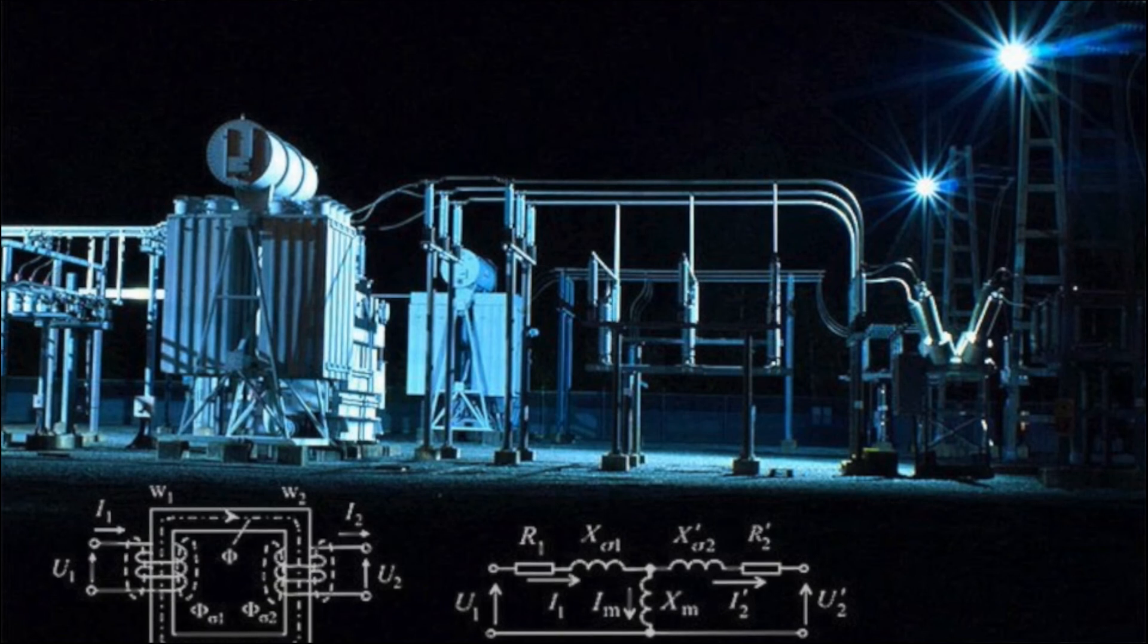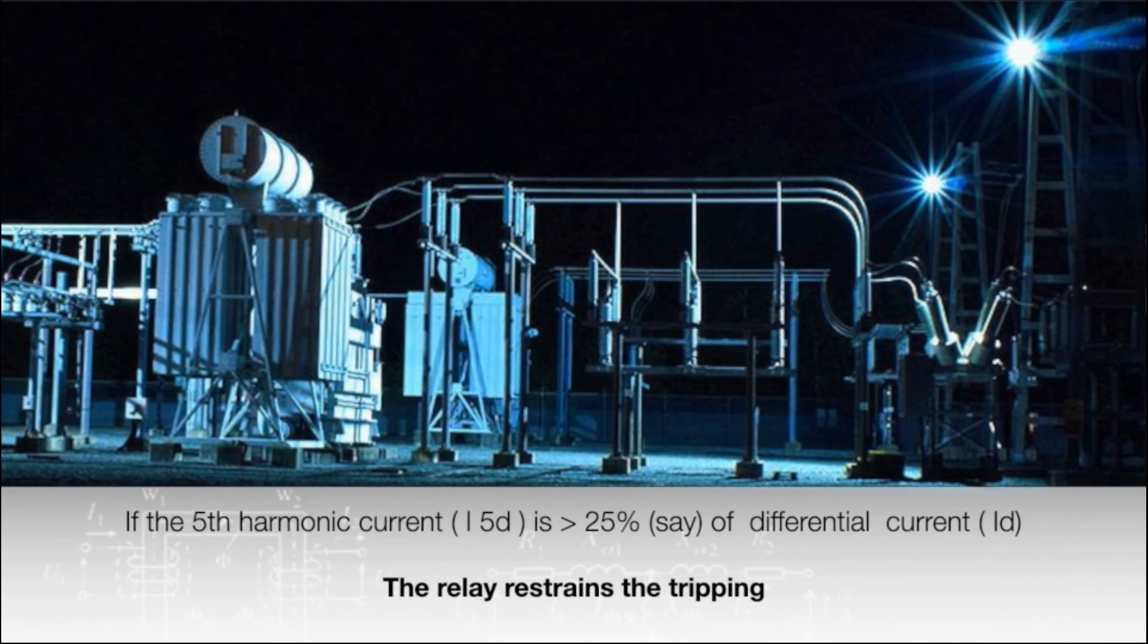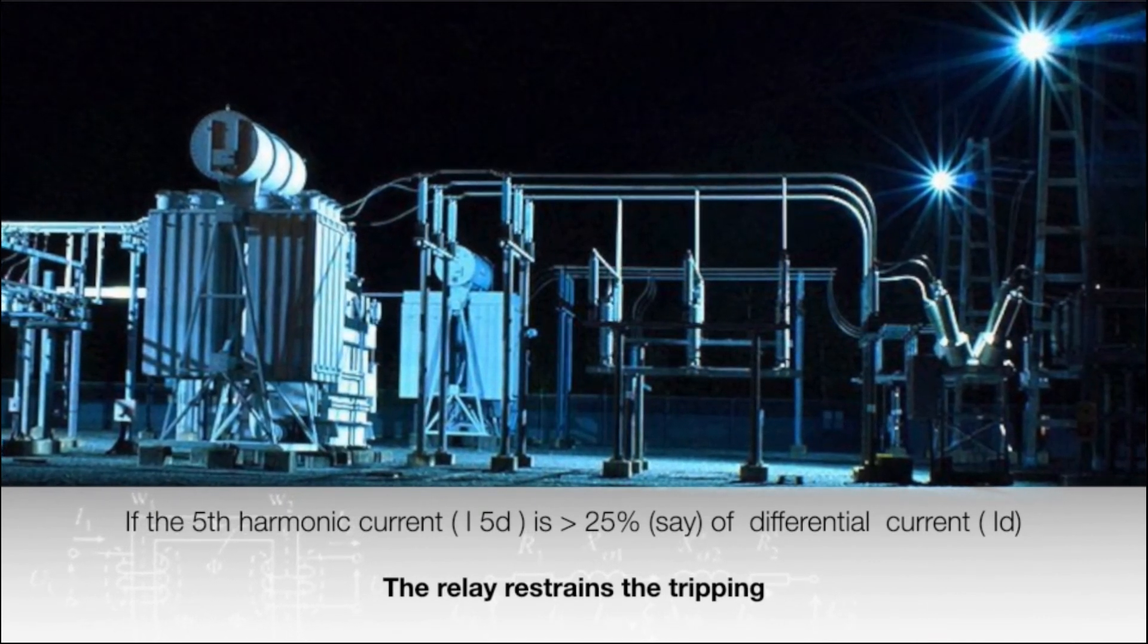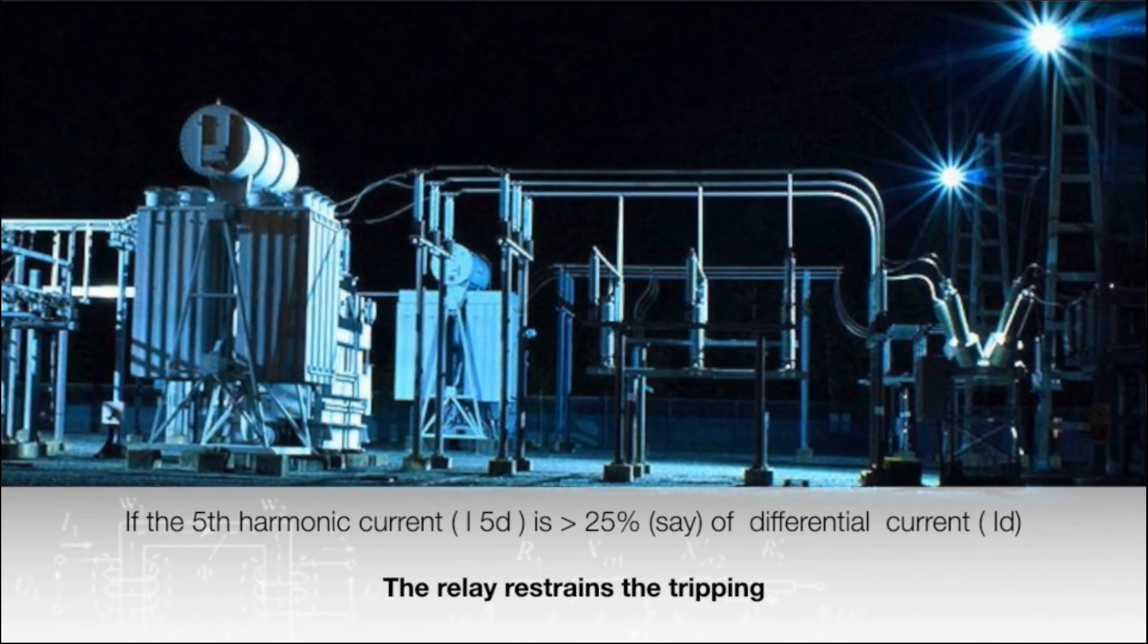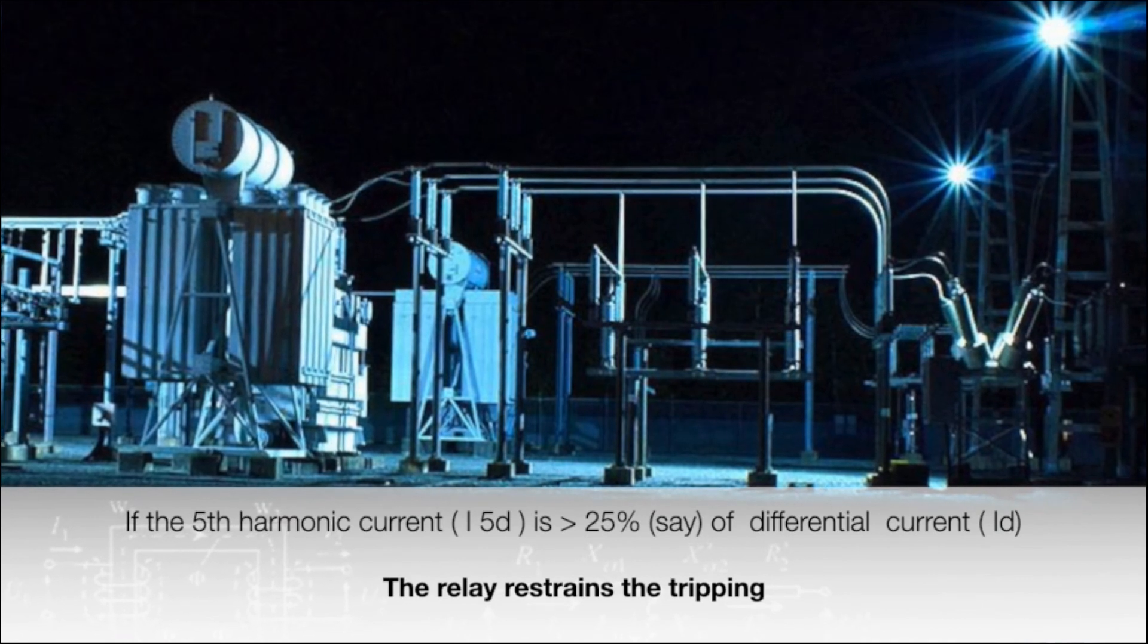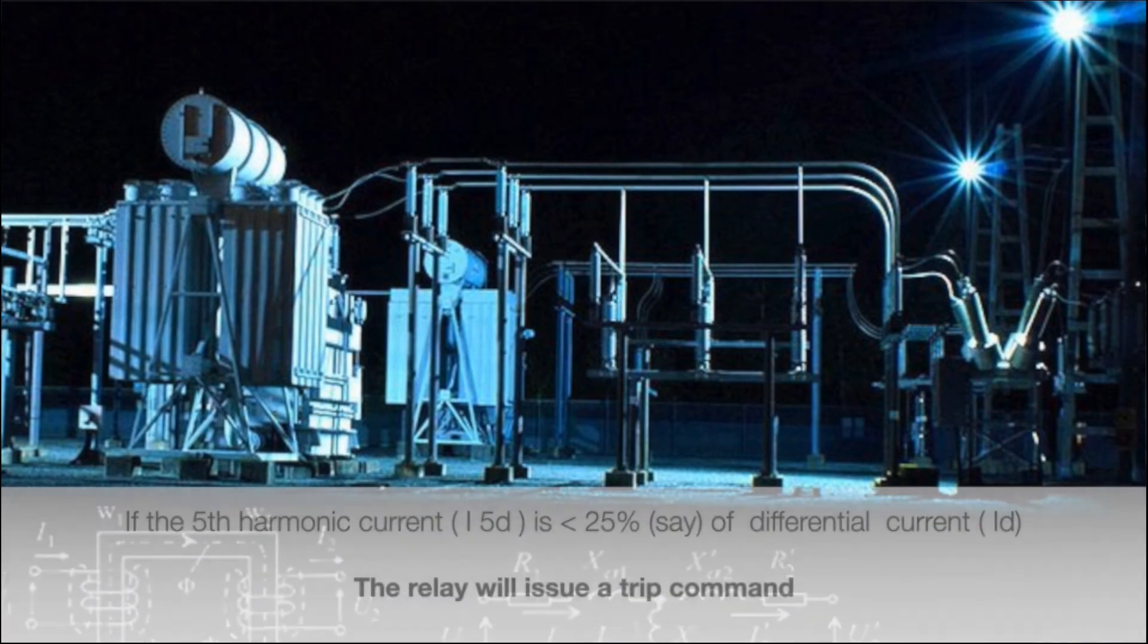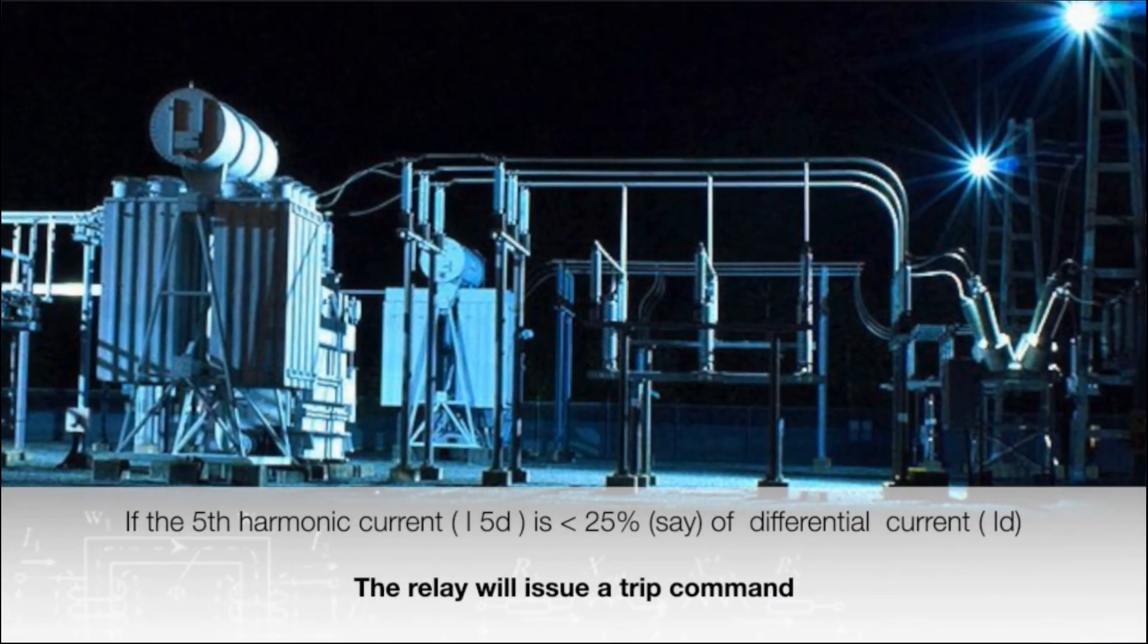Therefore, to prevent operation of differential relay due to over-fluxing, fifth harmonic restraint is provided in such a manner. If the fifth harmonic component in differential relay is more than 25%, then the differential protection relay will not operate. If this harmonic component in differential relay is less than 25%, the relay will operate.